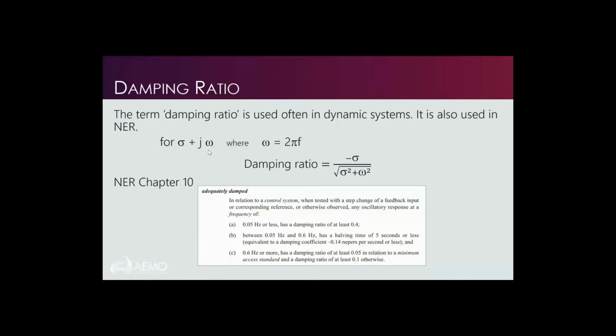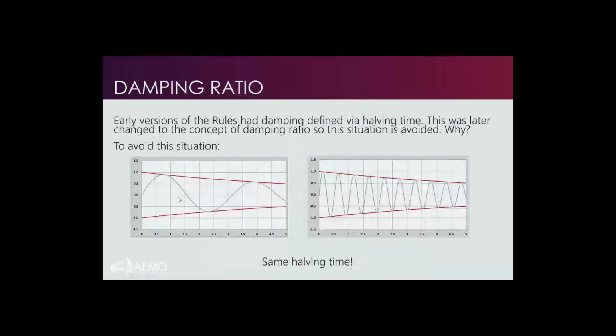A halving time of 5 seconds is still used for frequencies between 0.05 and 0.6 hertz. Halving time is the time needed for the amplitude to halve. Some people will know that before the damping ratio requirement, an earlier version of the rules required the response halving time to be 5 seconds or less for all frequencies. The next slide will show why halving time for all frequencies in the early version of the rules was replaced by damping ratio for some frequencies.